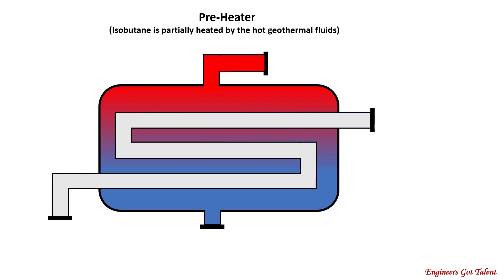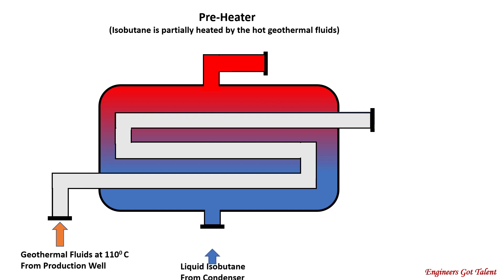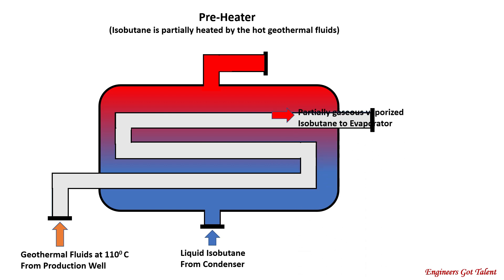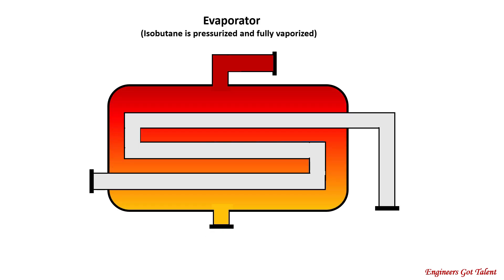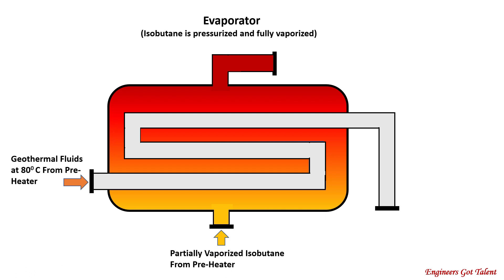Next is the preheater, which is a heat exchanger where the heat coming from the geothermal fluids is absorbed by the incoming liquid isobutane. The liquid isobutane boils and turns into partially gaseous vapor. The geothermal fluid exits the preheater at a lower temperature of 80 degrees Celsius. Next is the evaporator, also a heat exchanger, where the geothermal fluid continues to boil the partially gaseous vapor into 100% vapor.